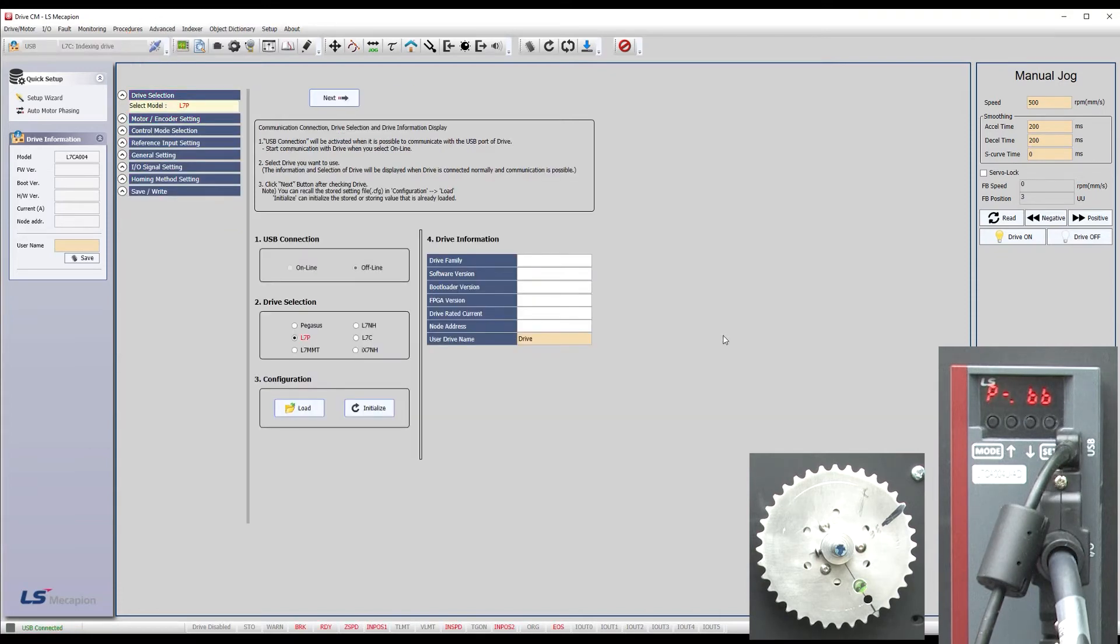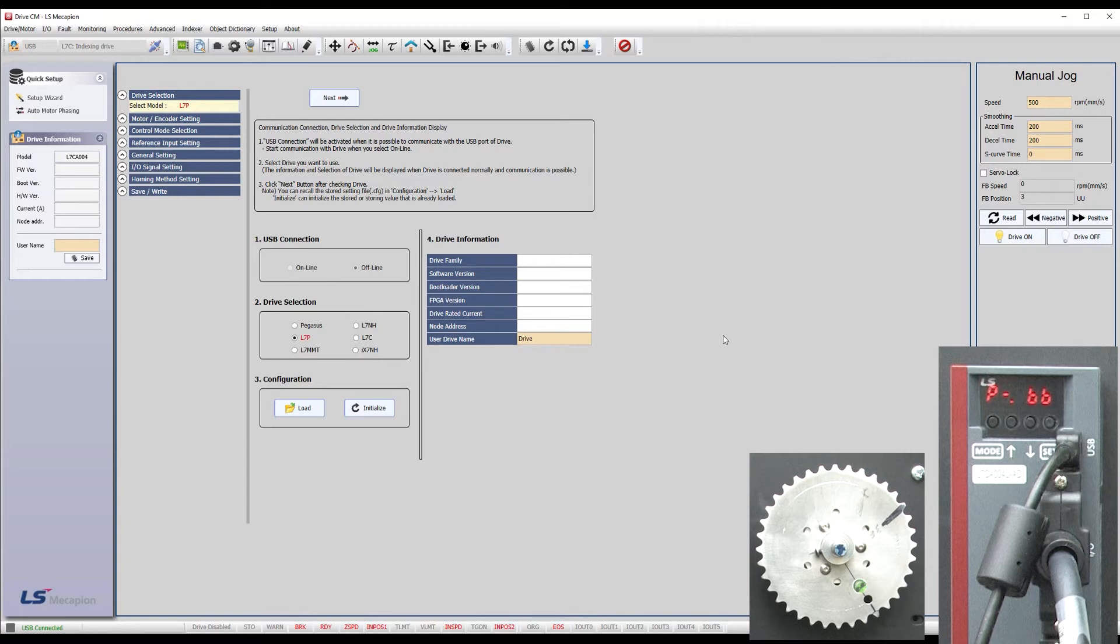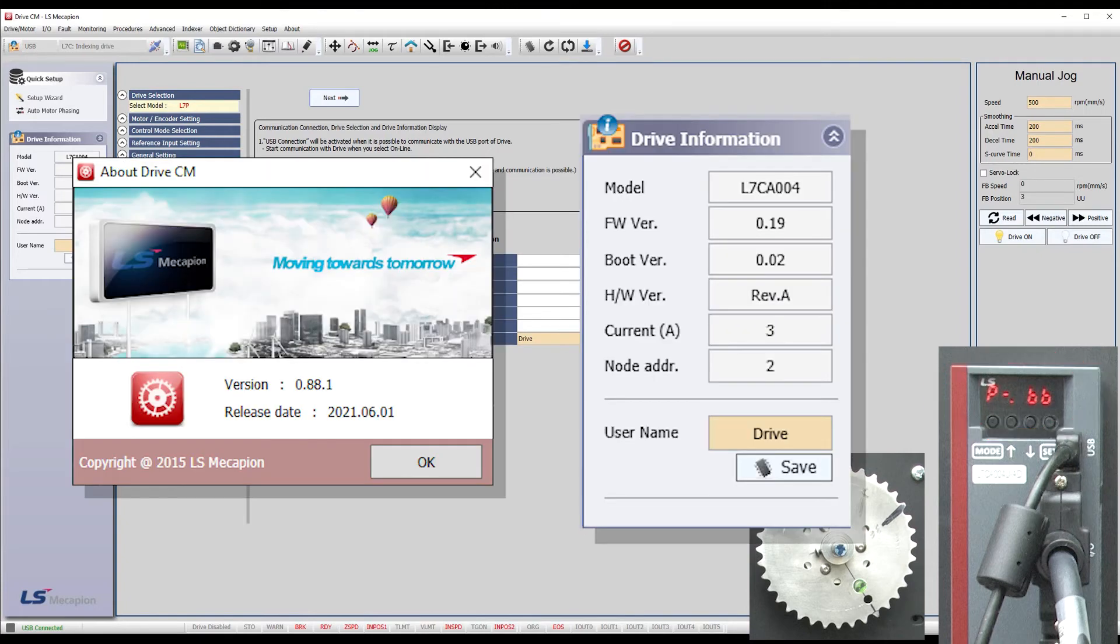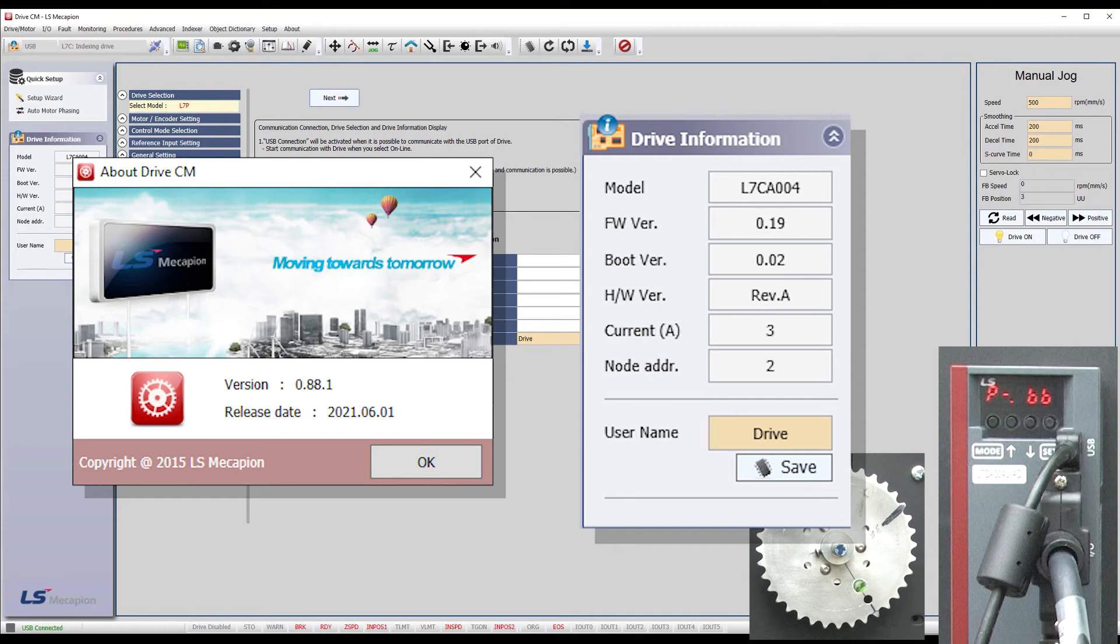Again, if indexing doesn't work, it's probably because you missed this controller reset step. So, we did this reconfiguration step just to clear out the alarm condition because my version of the software and firmware don't seem to re-enable the motor after clearing the alarm. Hopefully you won't have to do that in future versions, but if you do, now you know how.